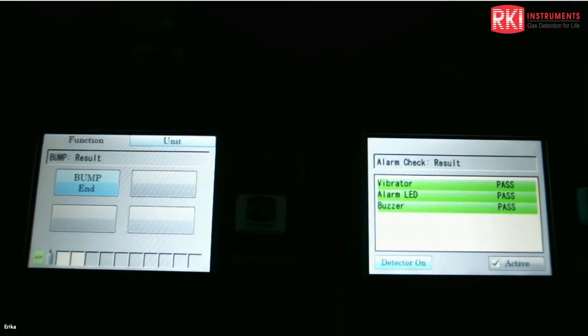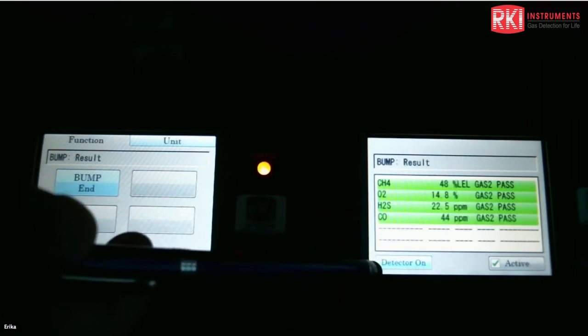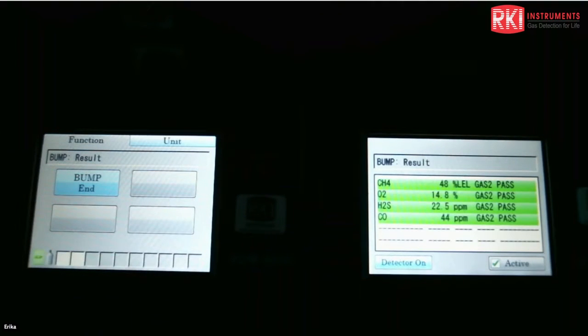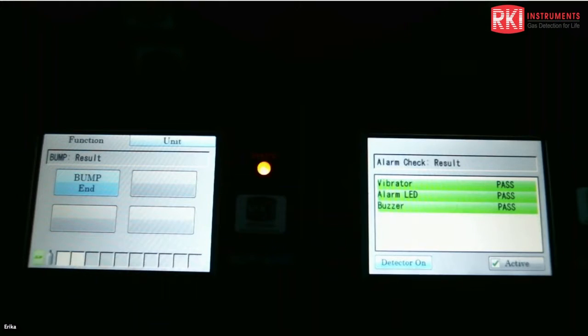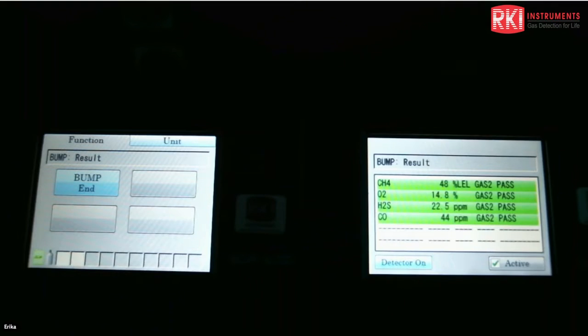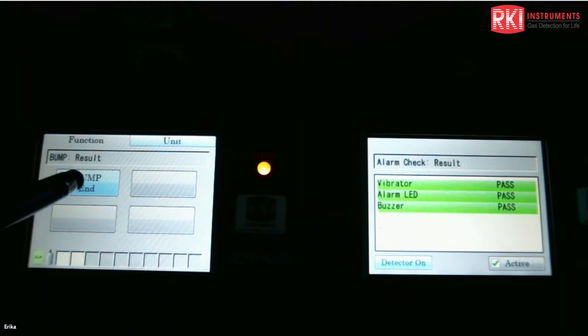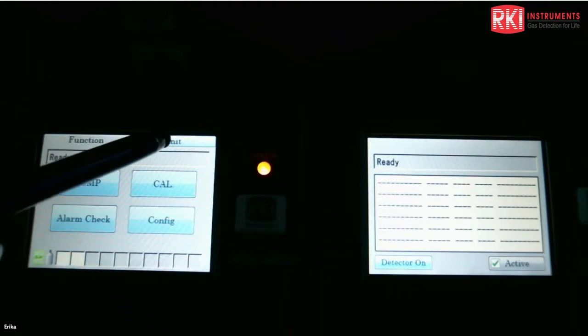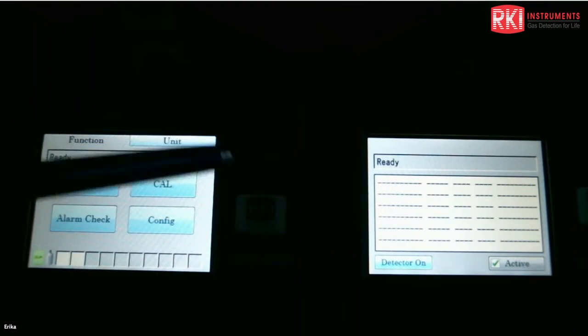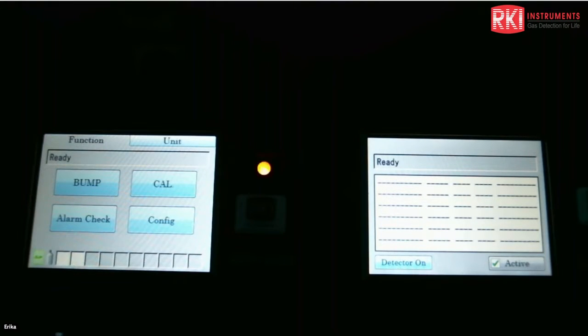And you can see on the second dock, it has a button that says detector on. That's telling you if you want to turn the detector on, you can press that button. And while it's on, it'll show detector off, meaning if you want to turn the instrument off. Once it completes a successful bump, it automatically turns them off right away. So I'll go ahead and hit bump end right now. And if I actually want, for example, to calibrate the first dock but not the second dock, I could just click this active button right here, which I would need to turn the detector on first.